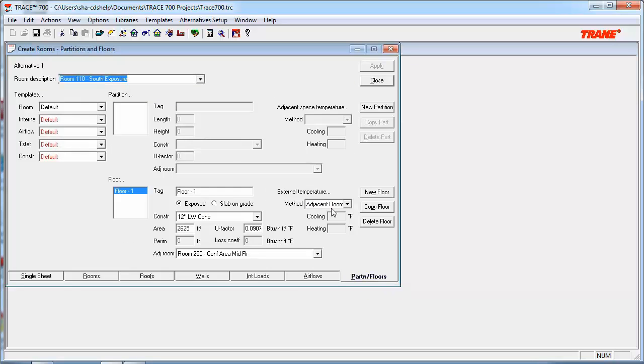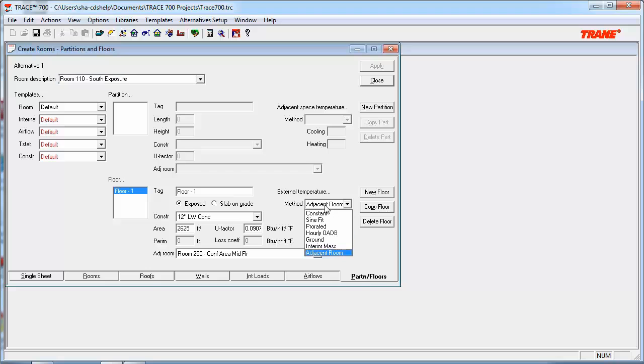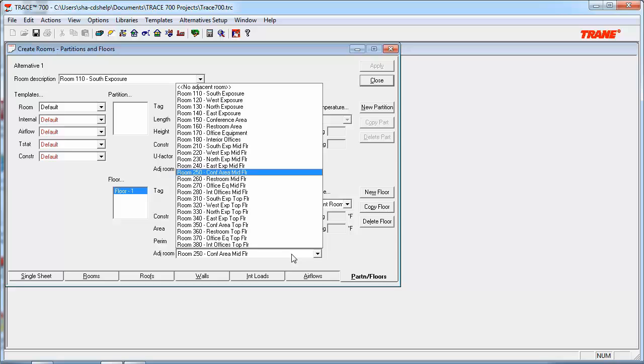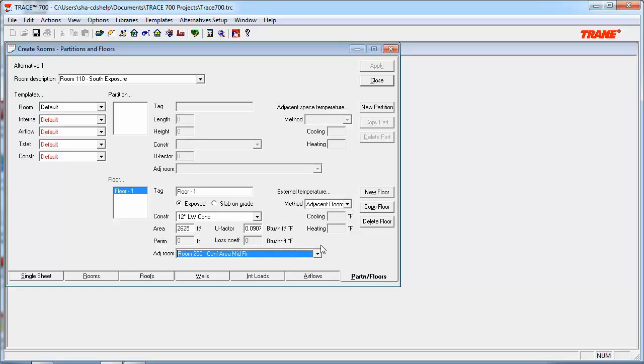Finally, let's look at the Partition Slash Floors tab. This is where you can input a floor in between the spaces to model the appropriate heat transfer for underfloor plenums. When you create a floor, input the proper characteristics of the floor and select the external temperature method to adjacent room. You will then need to select the room that is below this current room through this input here. For heat transfer between the current room's underfloor plenum and the ceiling return air plenum of the room below, the heat transfer occurs directly between the subfloor separating the two spaces. However, if the current room has a plenum intervening between it and the adjacent room below, the heat transfer from the adjacent floor is transferred into the plenum.